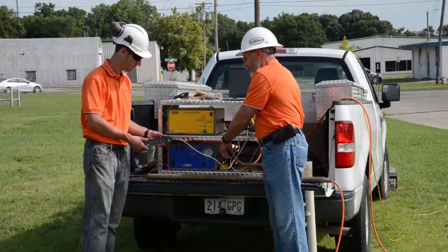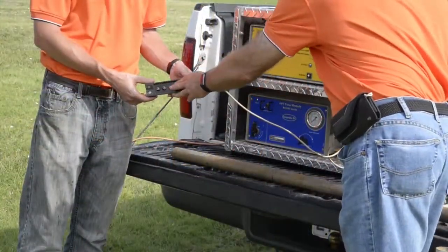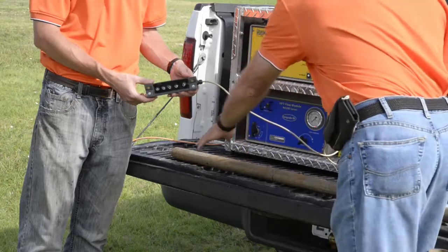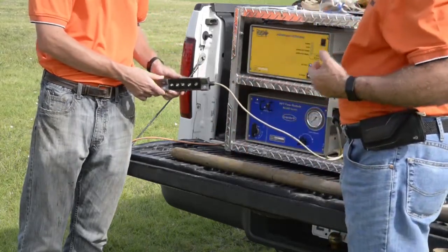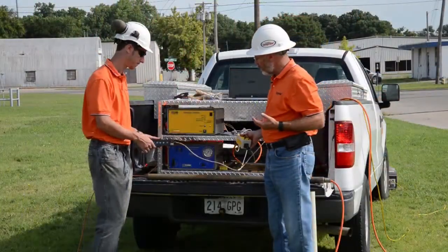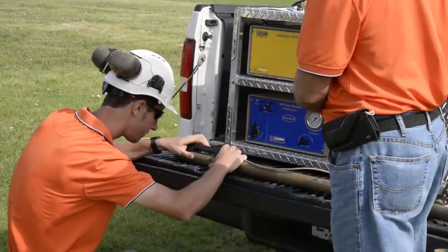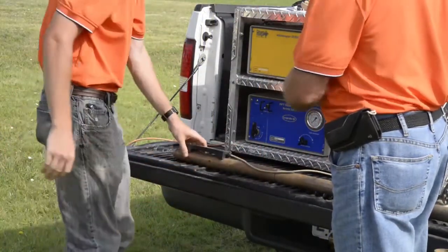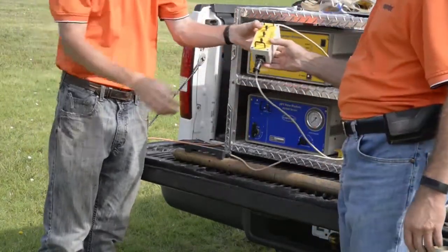This is the test jig for the EC. You see we have 5 electrodes on this, springs, and those will attach to each of the electrodes and one to the body of the probe. The body is the ground for the EC array. Ben will go ahead and install that there. And there are magnets on that to help hold it on the probe. And then we have our test load here.